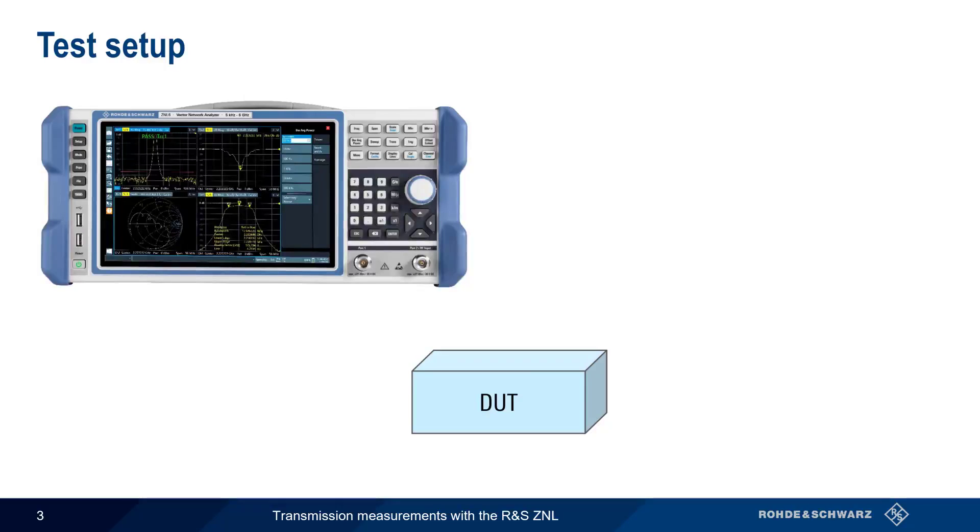The typical test setup for two-port measurements is very simple. We just connect the two ports on our ZNL to the two ports on our Device Under Test, or DUT.